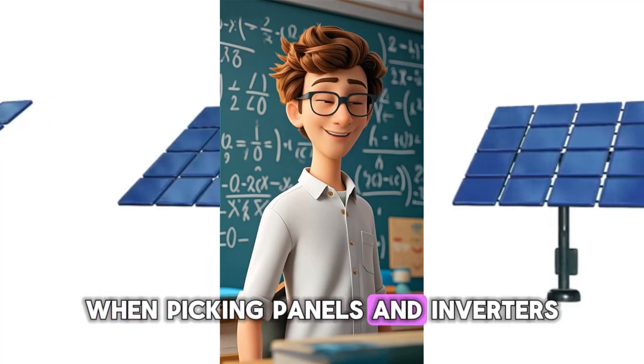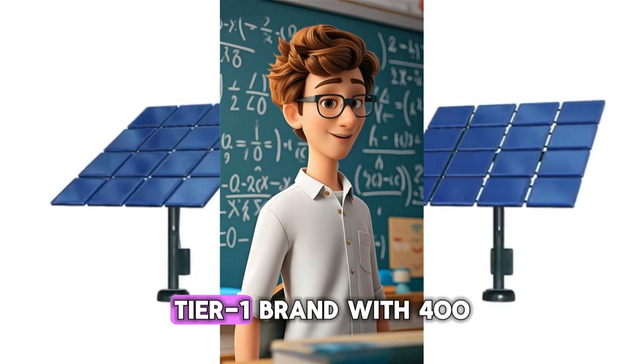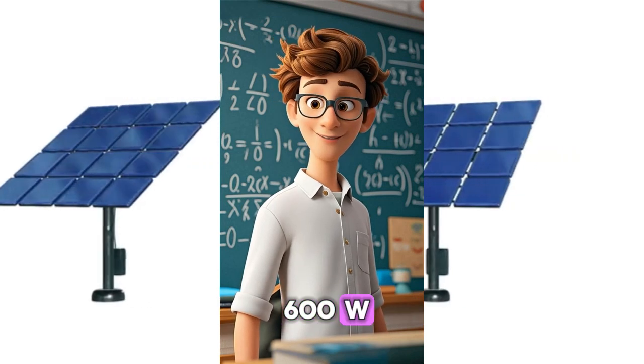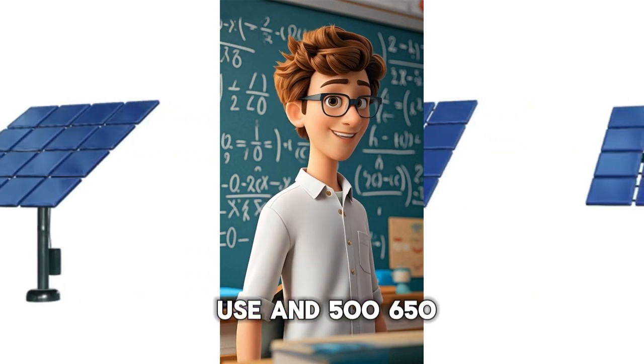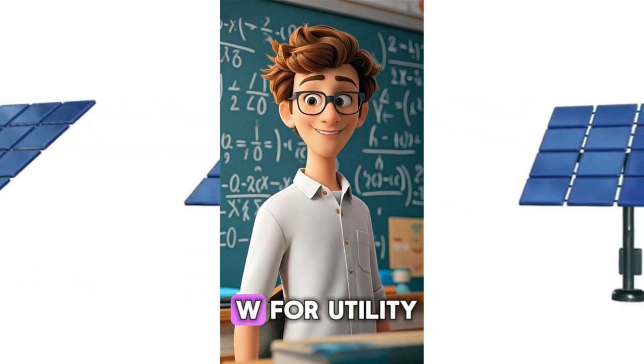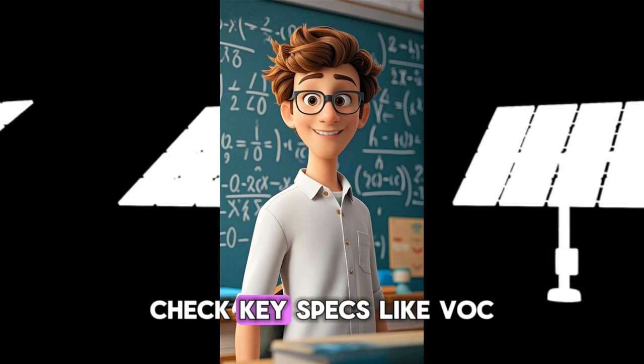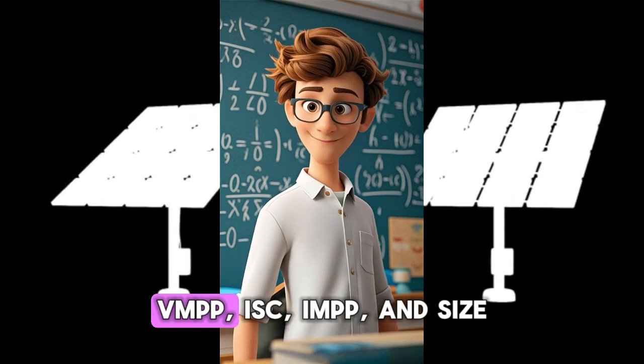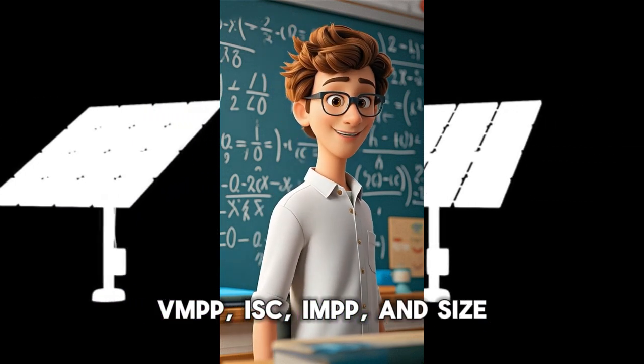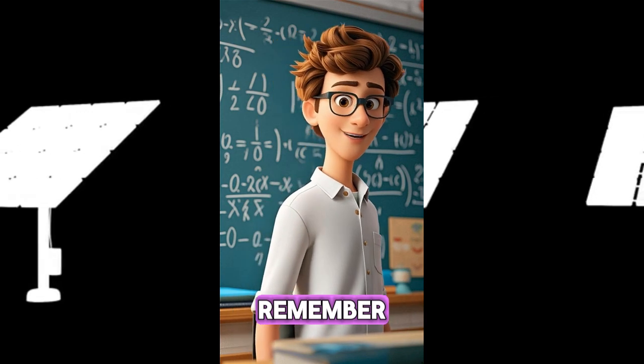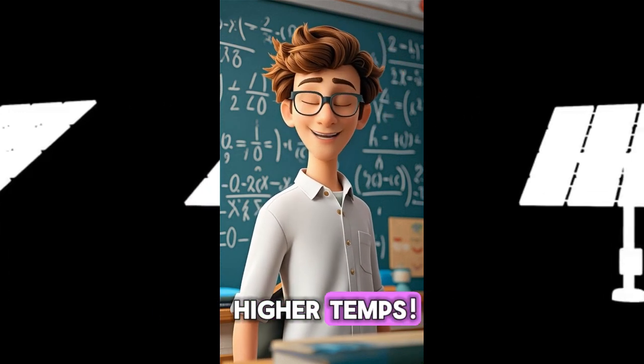When picking panels and inverters, go for a solid Tier 1 brand with 400-600W for residential or commercial use and 500-650W for utility. Check key specs like VOC, VMPP, ISC, IMPP, and size. Remember, real voltages drop at higher temps.